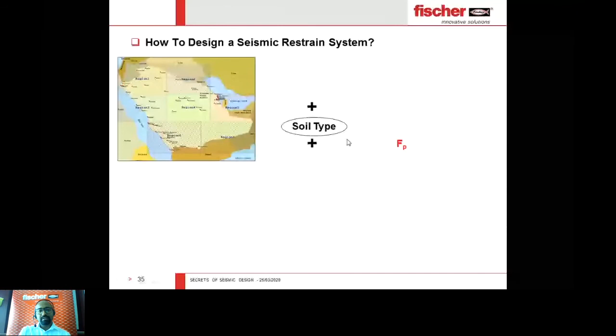For a seismic restraint system for MEP, we need to know certain parameters for design, such as soil type, building height, MEP service type, project importance category, and location. Based on this we calculate the horizontal force acting on the MEP. Normally the seismic force is a ratio of the dead weight or service weight of the application. For example, if you have a pipe that is 100 kg per meter, your seismic force is normally a ratio of this 100. Let's say upon calculation we find the seismic ratio is 0.3, meaning there is a 30 kilogram seismic load on this particular pipe.